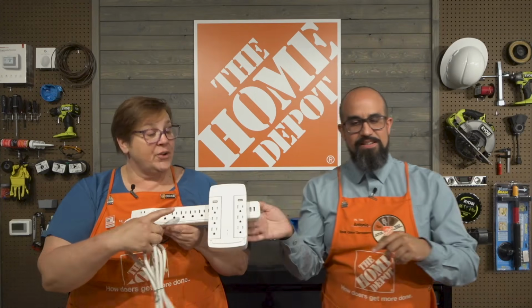The other thing is these provide more outlets, but they don't provide more electricity. That circuit still only has 15 or 20 amps to it. So if you try to overload it, it's going to trip the breaker, whether it's in the surge protector or not. This is not adding any more electricity to that circuit - it's just protecting the equipment.